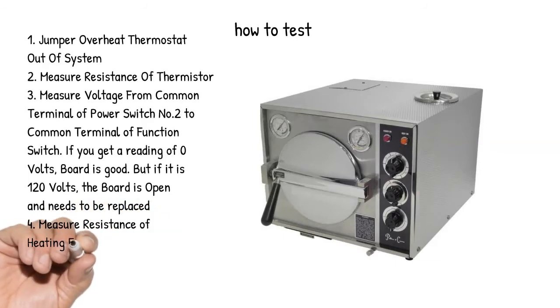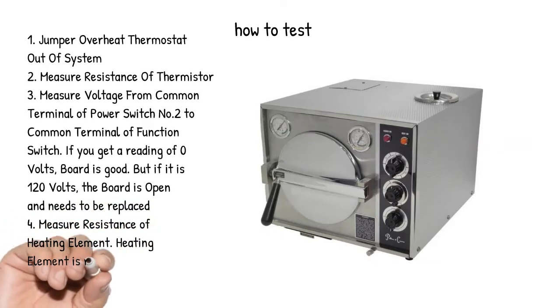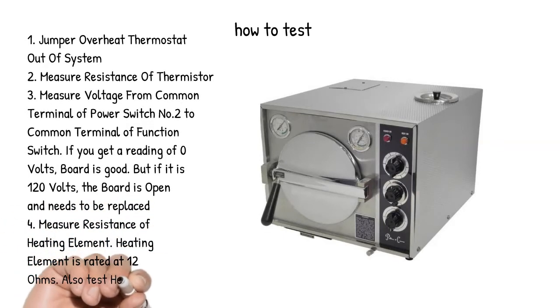4. Measure Resistance of Heating Element. Heating Element is rated at 12 Ohms. Also test Heating Element for a Direct Short.